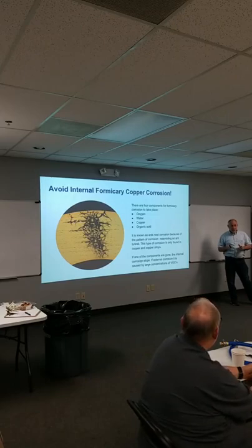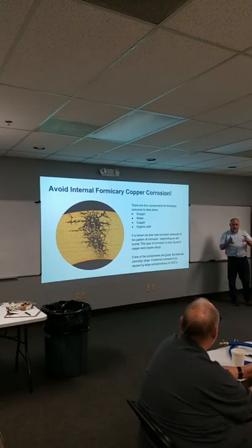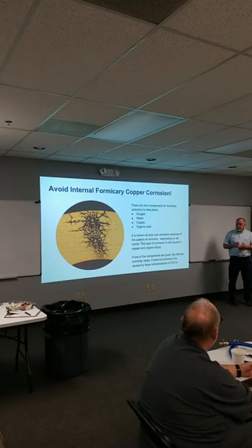Why? Well, because the guys at Copeland know about evacuation. They evacuated every system before they put the stuff in, they tested it, it works great. The guys in the field, they're gas and go guys. They're not evacuating. They're cracking the service valves open. There's so much moisture and stuff that the chemical plant takes off, and it's actually building up wax and all kinds of other crap that's plugging up the inlet screens to these TXVs. Copeland never saw that coming, right? So these kinds of things happen when we don't have good evacuation.